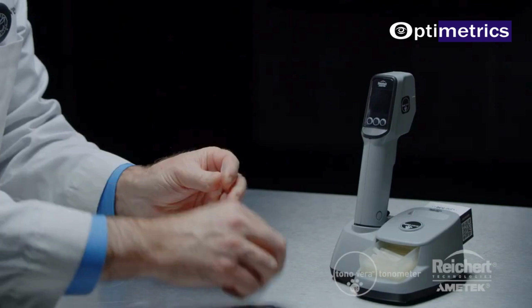The color of the ring indicates the reliability of the measurement. A green ring means you have a high confidence result. A yellow ring means you have a low confidence result. If you see an orange ring with an arrow inside it, this indicates that you should retake the measurement. The Tono-Vera Vet is equipped with Bluetooth, so you can quickly and easily send IOP results to your electronic medical records. You can clear out measurements for a single eye or clear out all the measurements at any time. To clear out all the measurements, press the clear button indicated by the X on the screen.